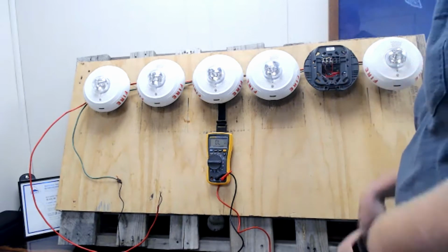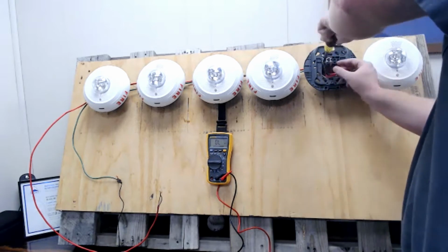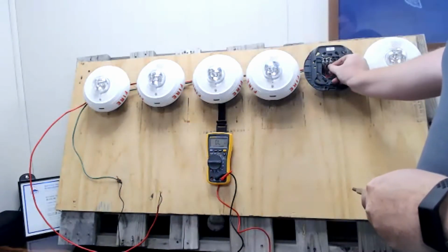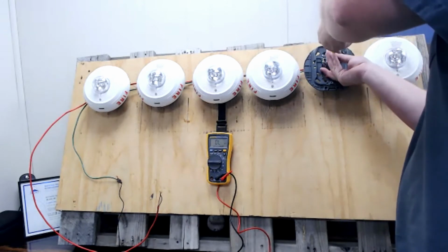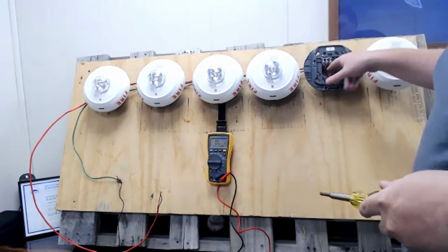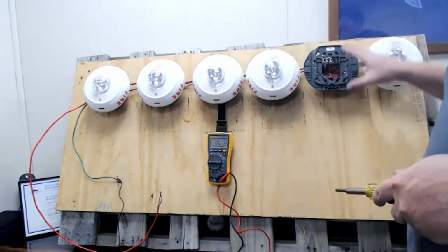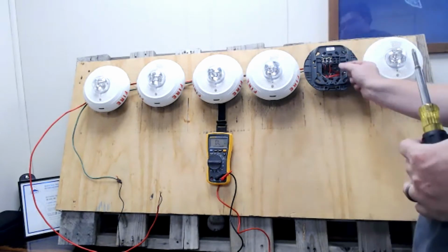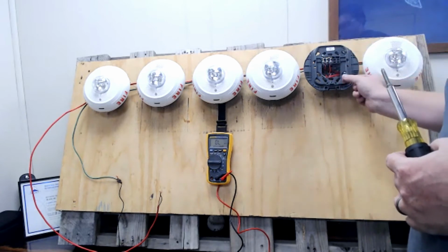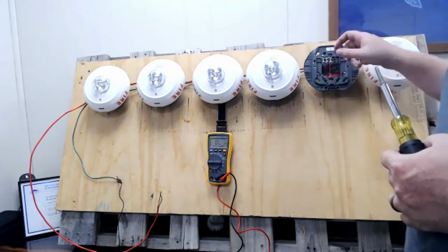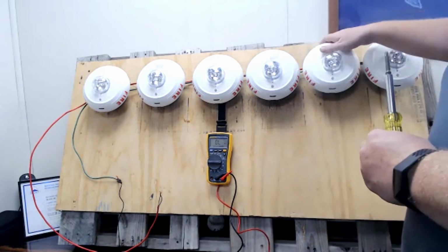So now I'm going to put this back together again, since I verified the repair. Verifying the repair is really important to do so that you don't end up just running back and forth like a chicken with your head cut off. All right, so I'm here, put all this in, I've pulled on it. So now I know all my conductors are in there solid. If you pull on it like that, it'll keep from having this type of open circuit that we just saw here, because having pulled on the wires, I'd know that that conductor was broken. So we've just fixed the open circuit condition that we had.